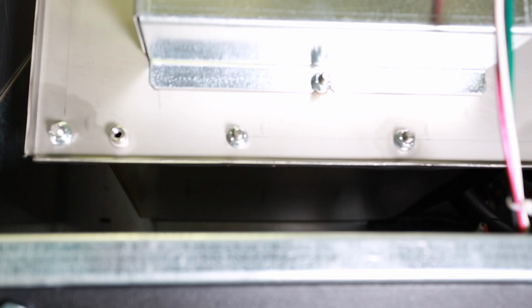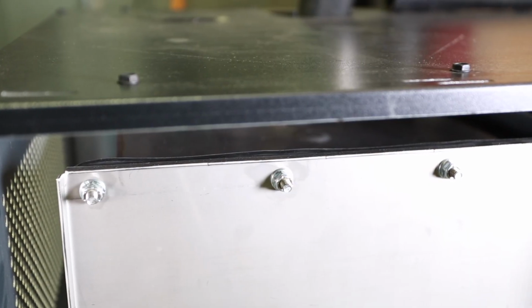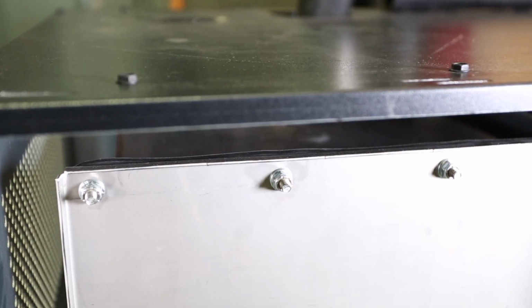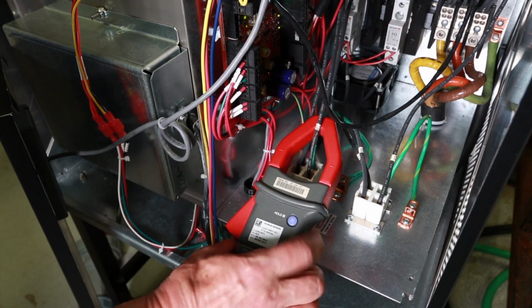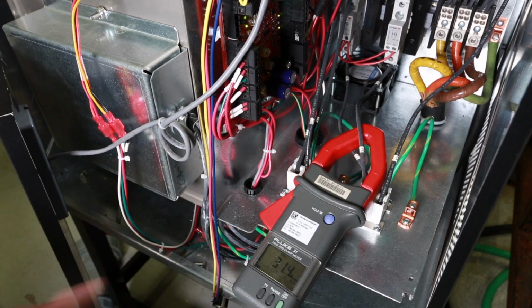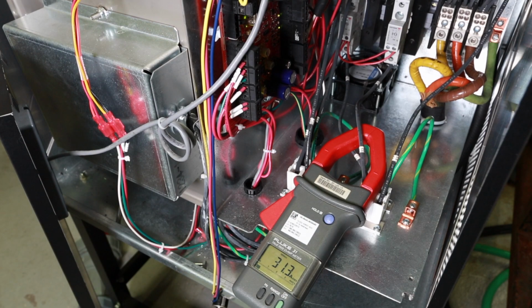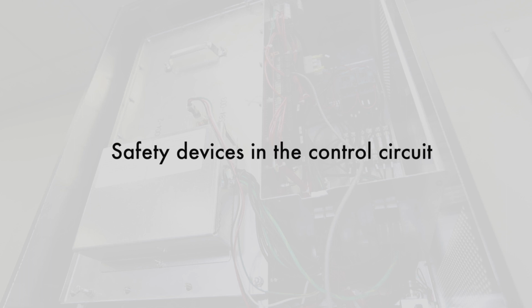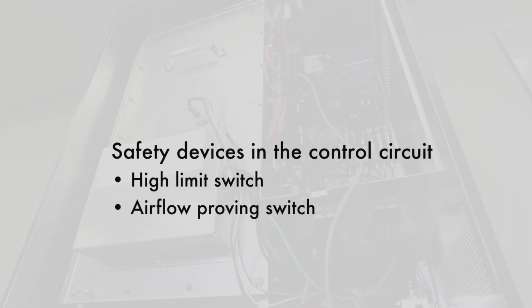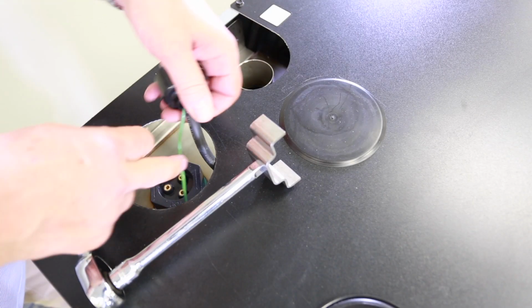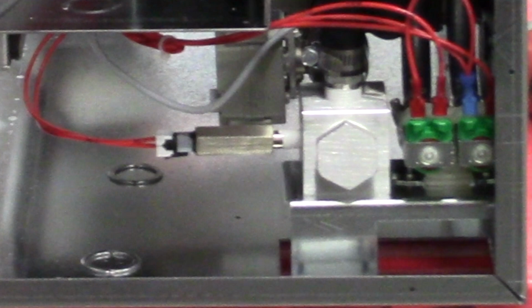At least annually, and whenever maintenance is performed, inspect the tank and gaskets for leaks. Measure current draw of heaters and verify amp values per stage by comparing to the wiring diagram located inside the sub-panel cover. This identifies any burned out heaters. All safety devices in the control circuit should be cycled on and off to verify they are functioning. These include high limit switch, airflow proving switch, and low water level probe. Pull out probe plug, and the fill valve should energize.